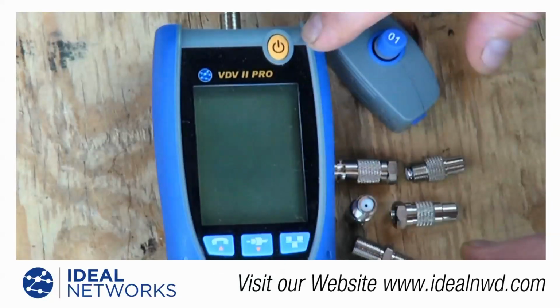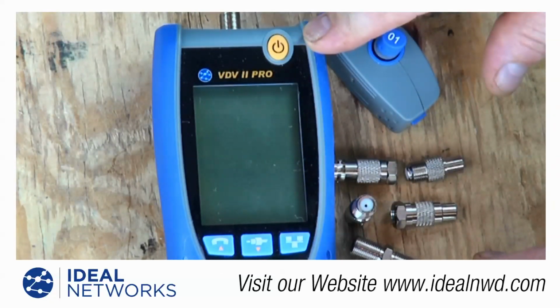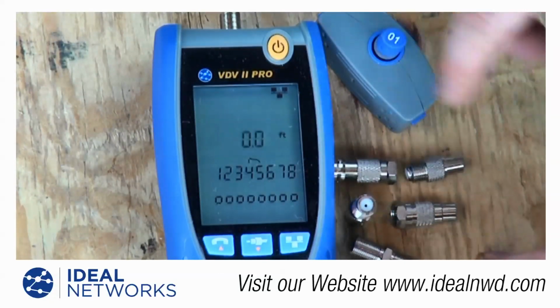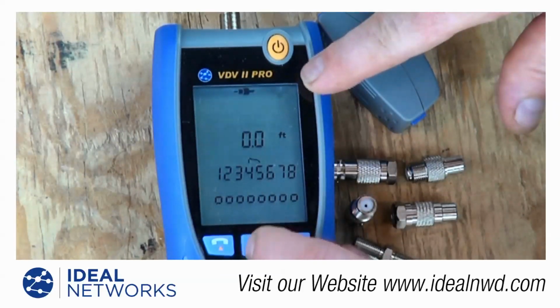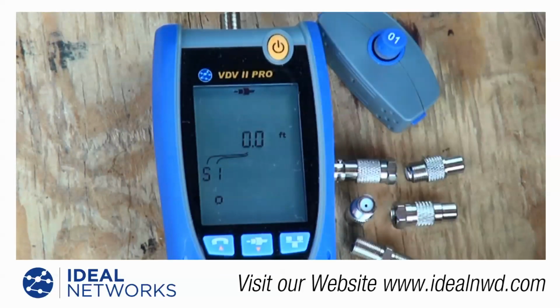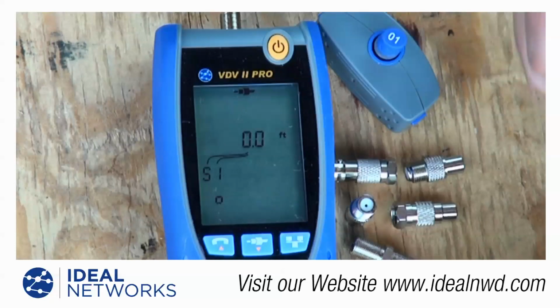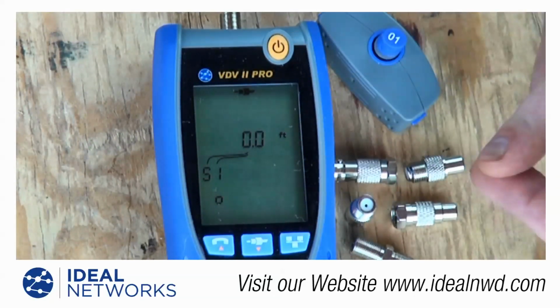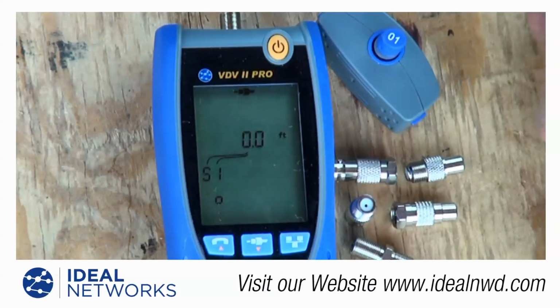To use the VDV Pro for testing coaxial cables, we'll very simply turn the tester on, and since I'm in the data mode, I'm going to push the coaxial icon until I get to the coaxial setting for the tester. Now, the tester does not measure signal strength. It's just going to check for opens and shorts and give you the length of a cable, as well as be able to ID a remote on the end of that cable so you know which end of that cable is connected to. So, again, length, ID a remote, and check for opens and shorts, but does not measure signal strength.